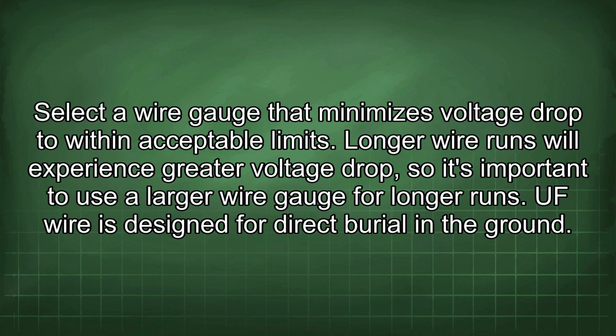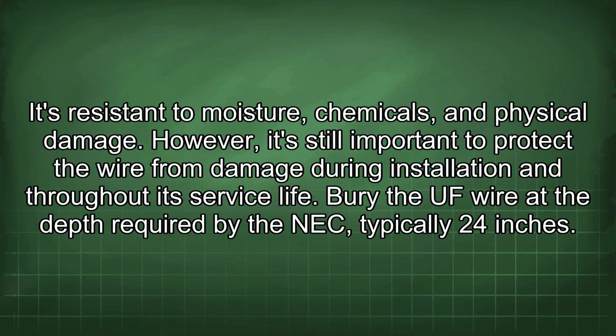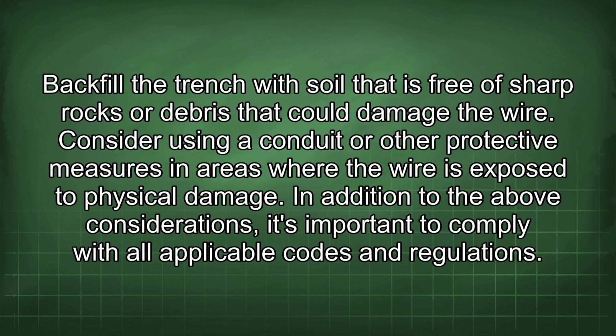UF wire is designed for direct burial in the ground. It's resistant to moisture, chemicals, and physical damage. However, it's still important to protect the wire from damage during installation and throughout its service life. Bury the UF wire at the depth required by the NEC, typically 24 inches. Backfill the trench with soil that is free of sharp rocks or debris that could damage the wire. Consider using a conduit or other protective measures in areas where the wire is exposed to physical damage.